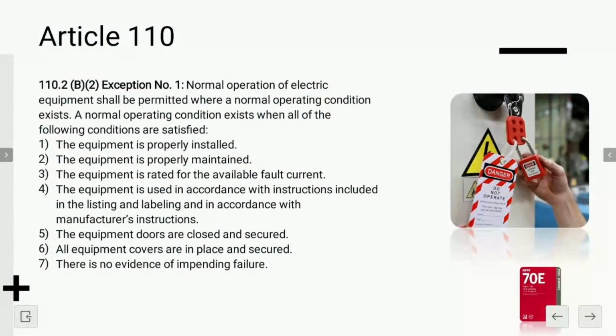Or the 70, the National Electrical Code. We also have to look at it and see if it appears to have any evidence of impending failure. And I'll show you some examples of what that would be like. And we have to make sure it's been properly maintained. And to do that, we have to talk to the owner and ask for maintenance records, right? Because sometimes they haven't maintained it. Okay, so we can operate equipment normally with all the covers on. All the doors are closed, not just the dead front, but the cover of the panel. And we've made sure it's properly installed, it's properly maintained. There's no evidence of impending failure.